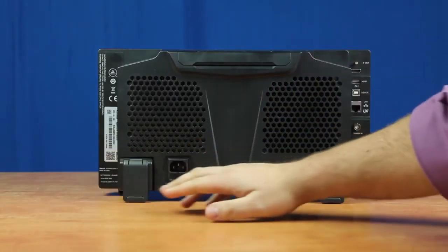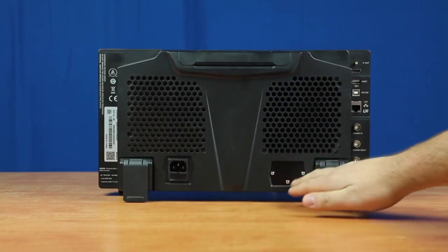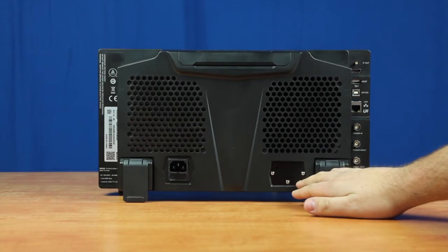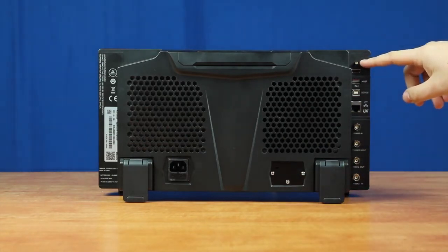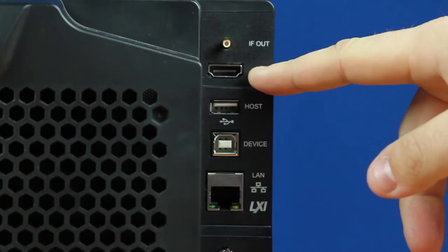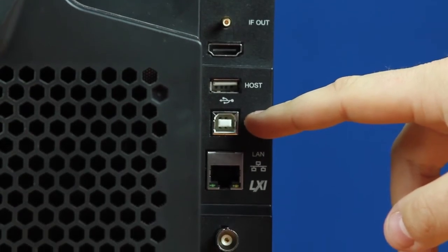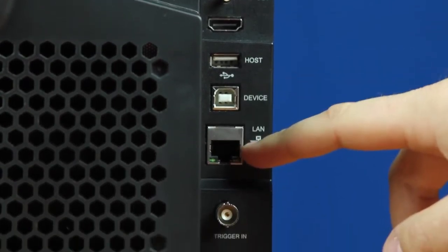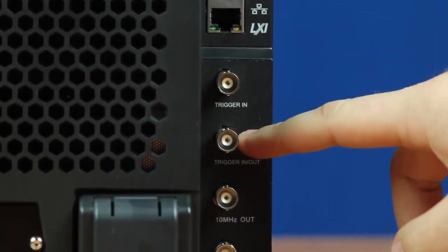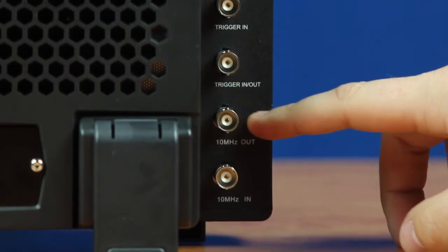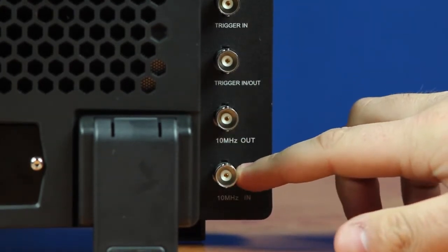On the back of the instrument, we'll find the serial number along with the power port and fuse cover. Then we can find the cover for where you can actually add an optional higher accuracy clock at any time. And right here we have our IF SMA connector, the HDMI port. Then we've got another USB host along with our USB connector, so you can control the instrument with your computer. Our LAN port, then 2 triggers, trigger ins, and this one can also be a trigger out.